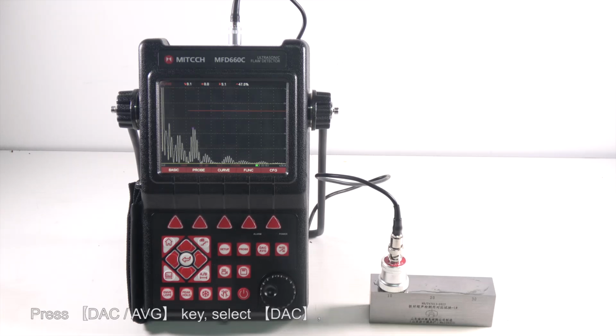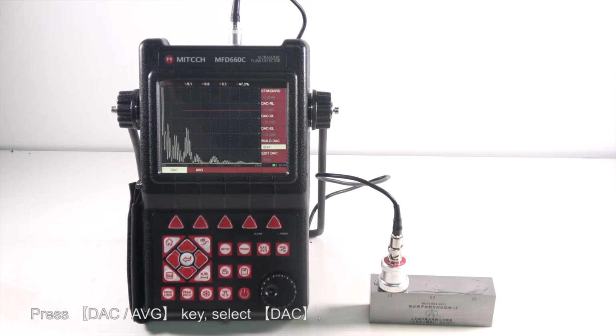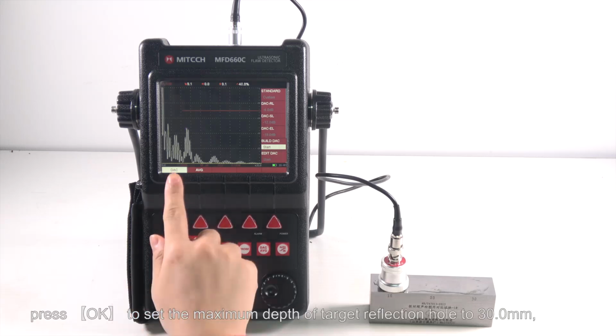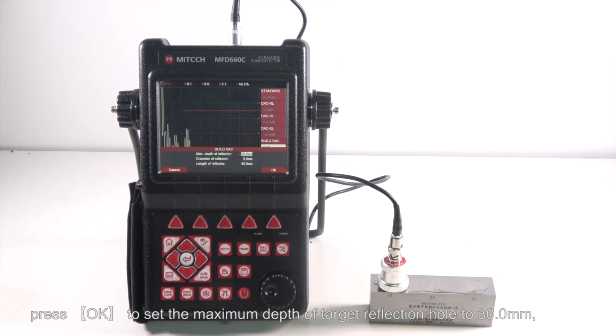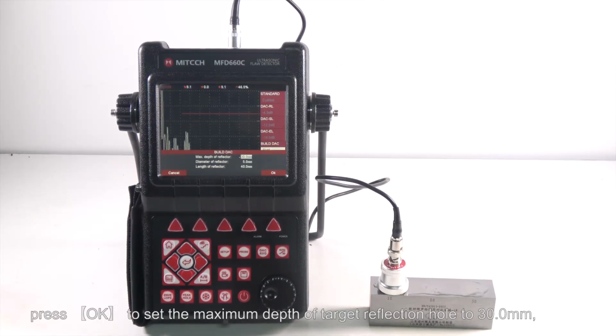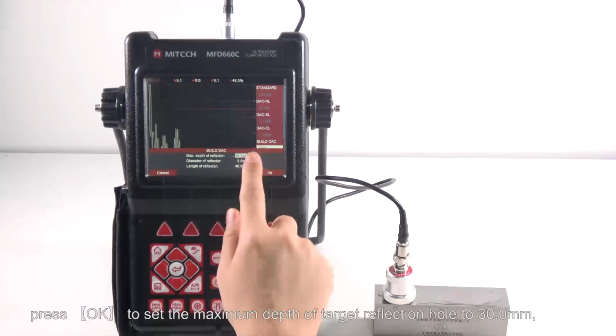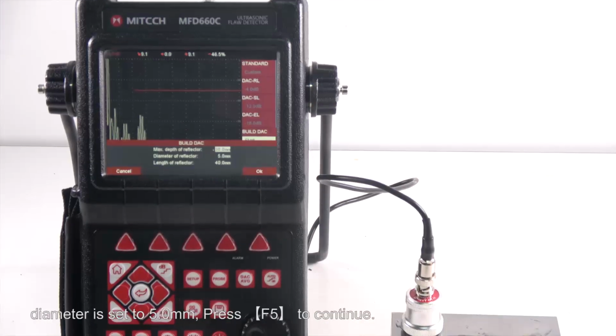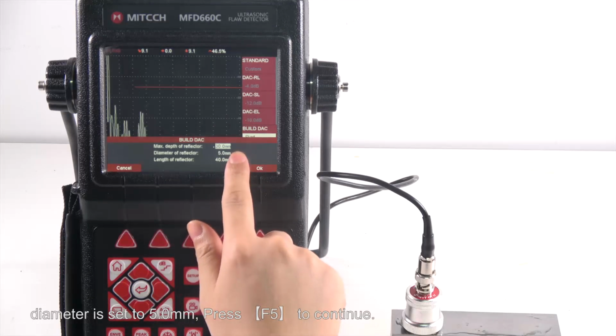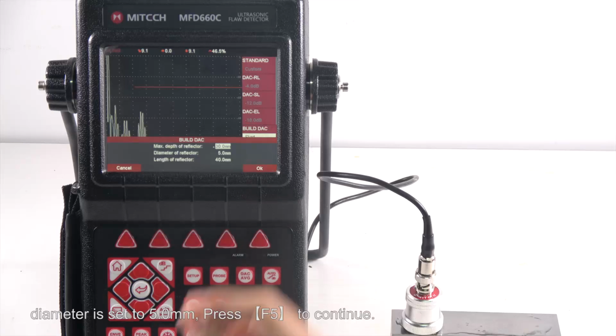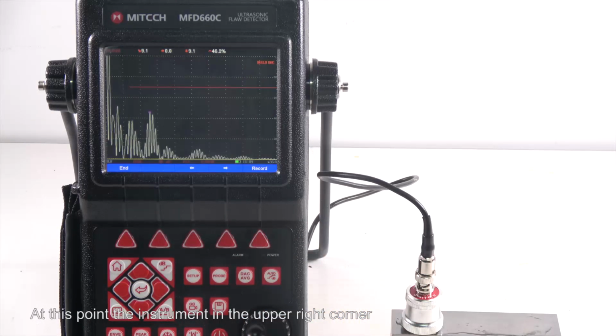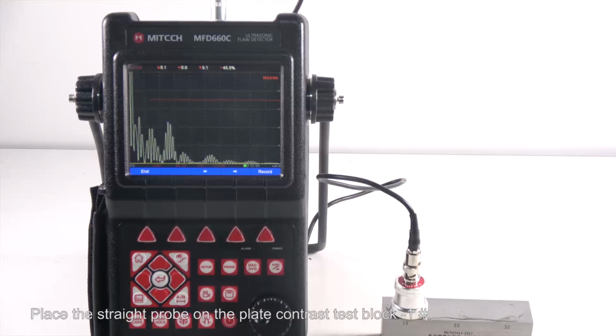Press the DAC AVG key. Select DAC. OK. Set the maximum depth of the target reflection hole to 30 mm. The diameter is set to 5 mm. Press F5 to continue. At this point, the upper right corner of the waveform display area shows that the DAC curve has been made into the state, and we begin to find the first measurement point. Place the straight probe on the plate contrast test block.